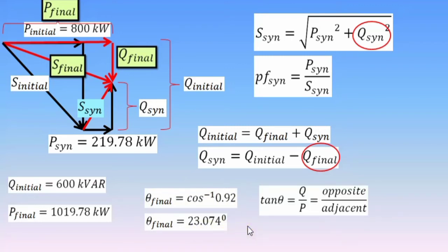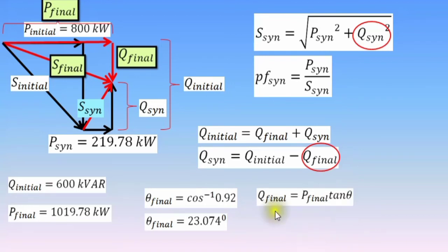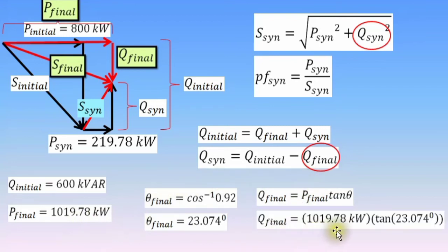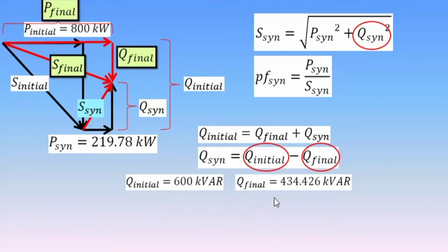Again, the relationship of the effective and reactive powers is tangent. So cross-multiply the effective power to the other side of the equation. Final reactive power equals final effective power times tangent theta. Effective power equals 1019.78 kilowatts. Substitute those values, we have 1019.78 kilowatts times tangent 23.074 degrees. Final reactive power equals 434.426 reactive kilovolt amperes.